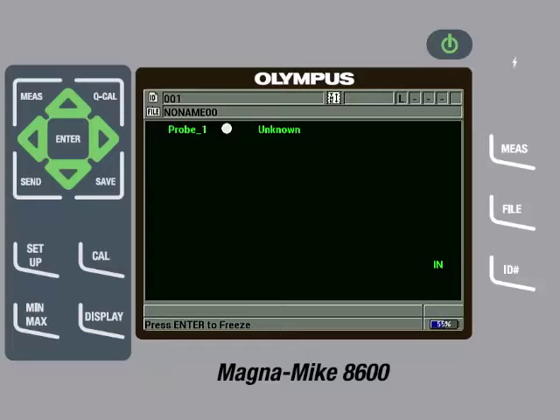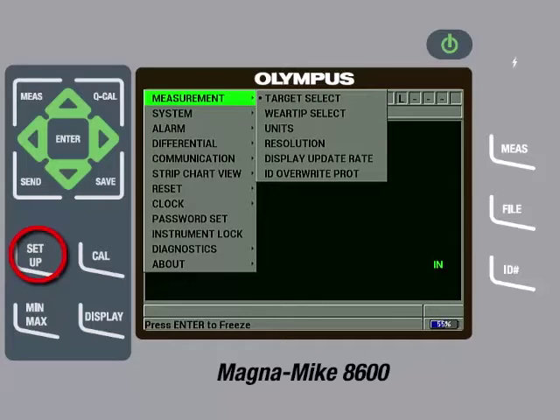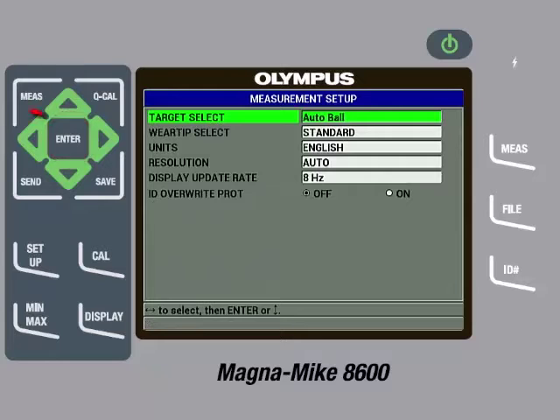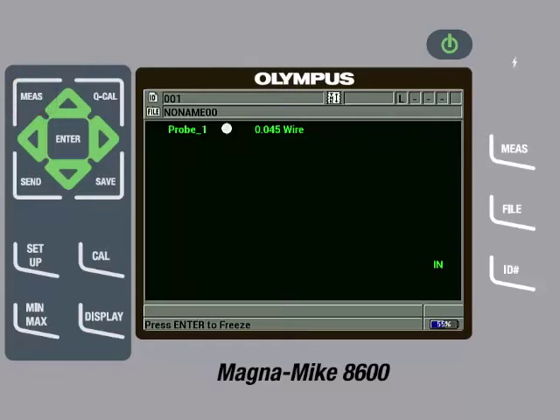To do this, press the Setup key. Then, with Measurement highlighted, press the right arrow so Target Select is highlighted, then press the Enter key. Press the left arrow until 0.045 wire is selected. Then press the Measure key. On the main measurement screen, the instrument will now display the target being used.